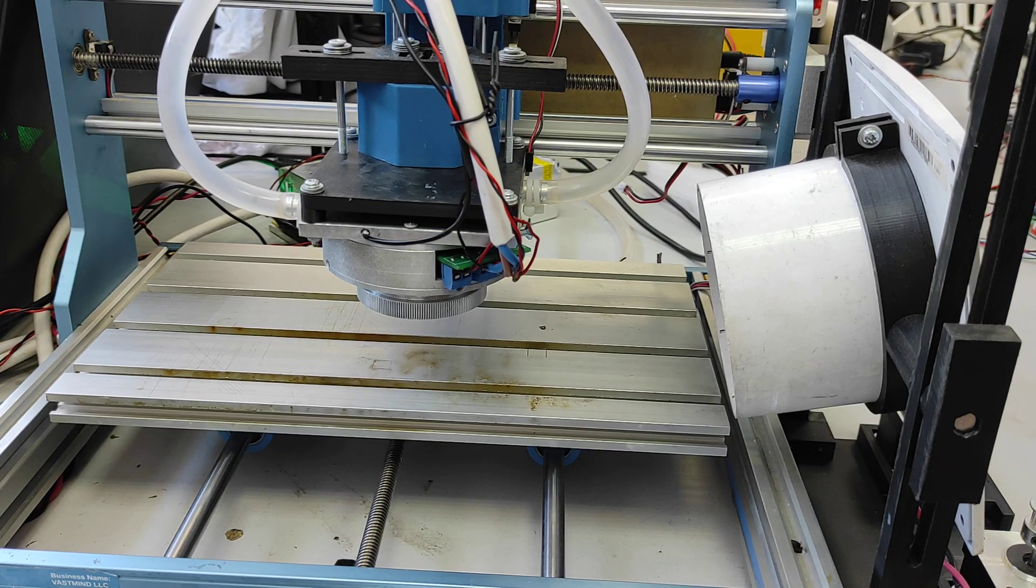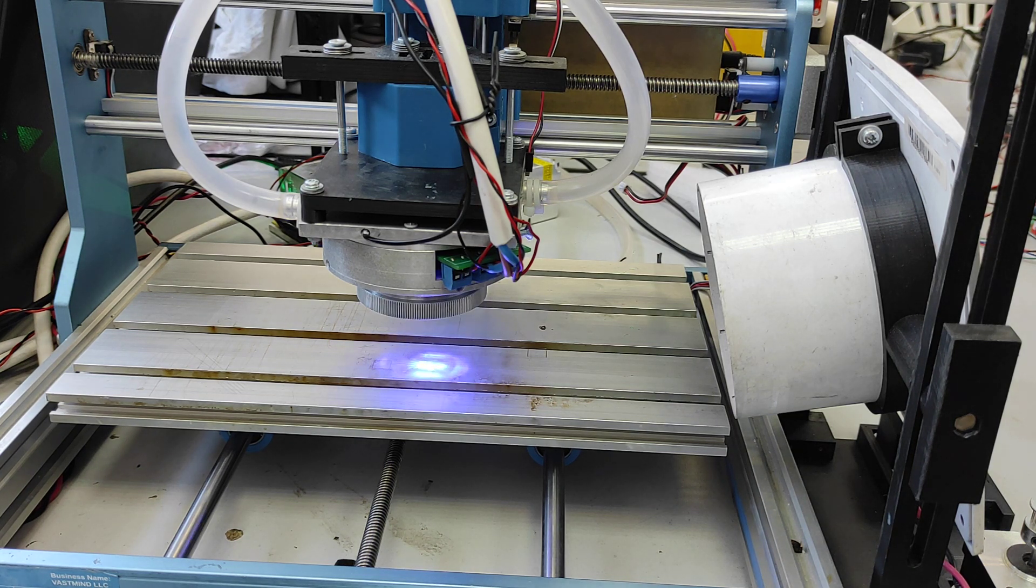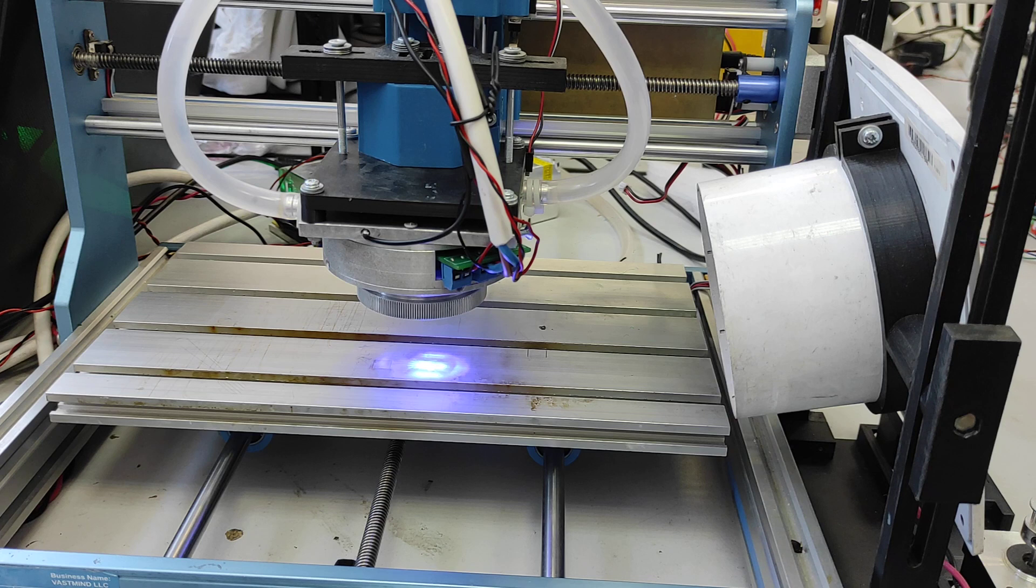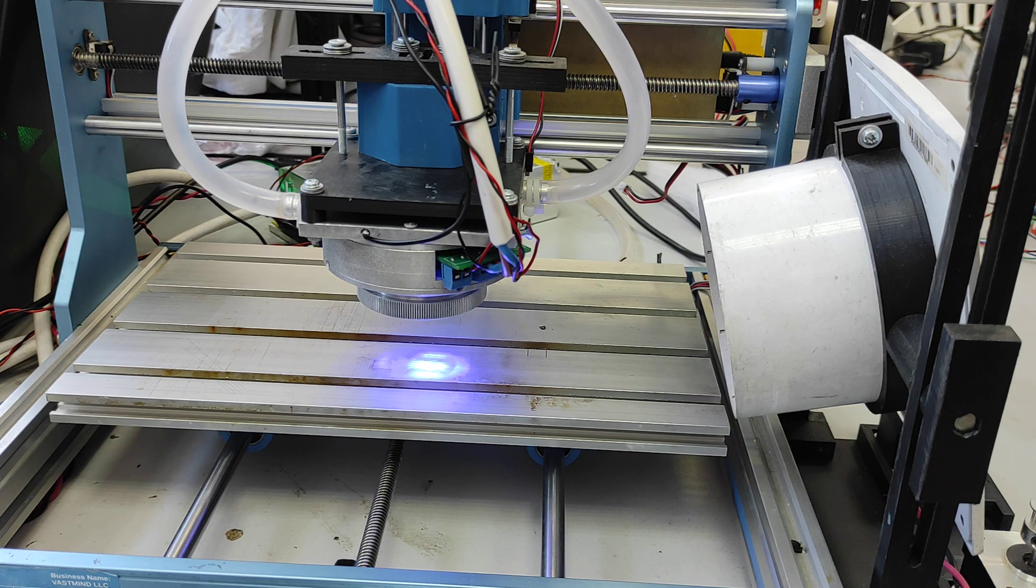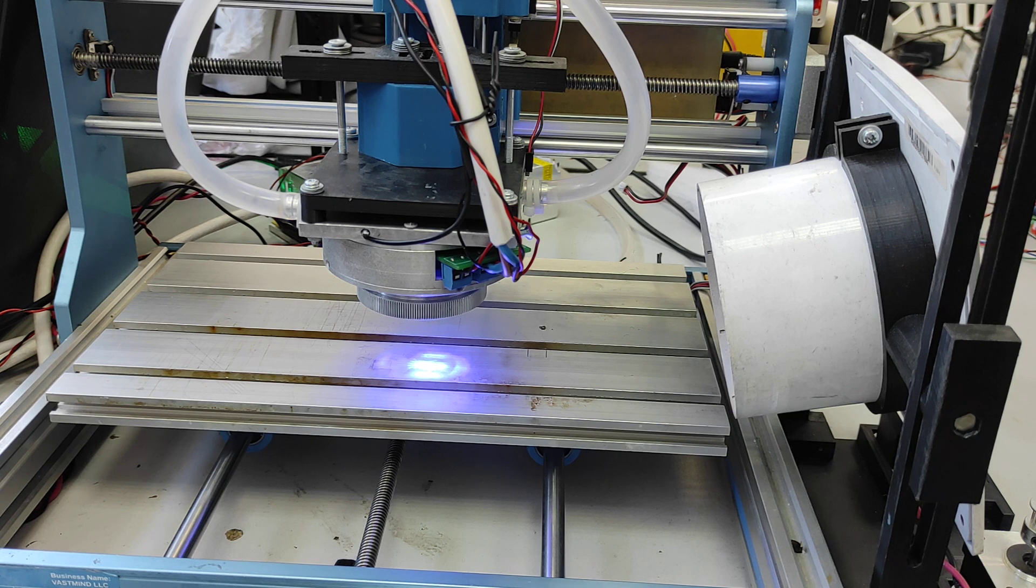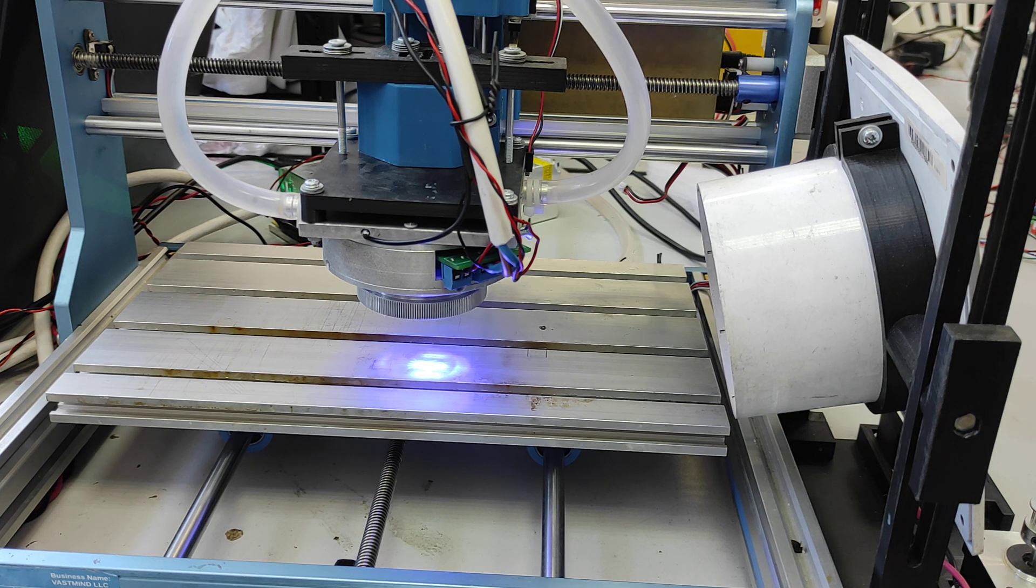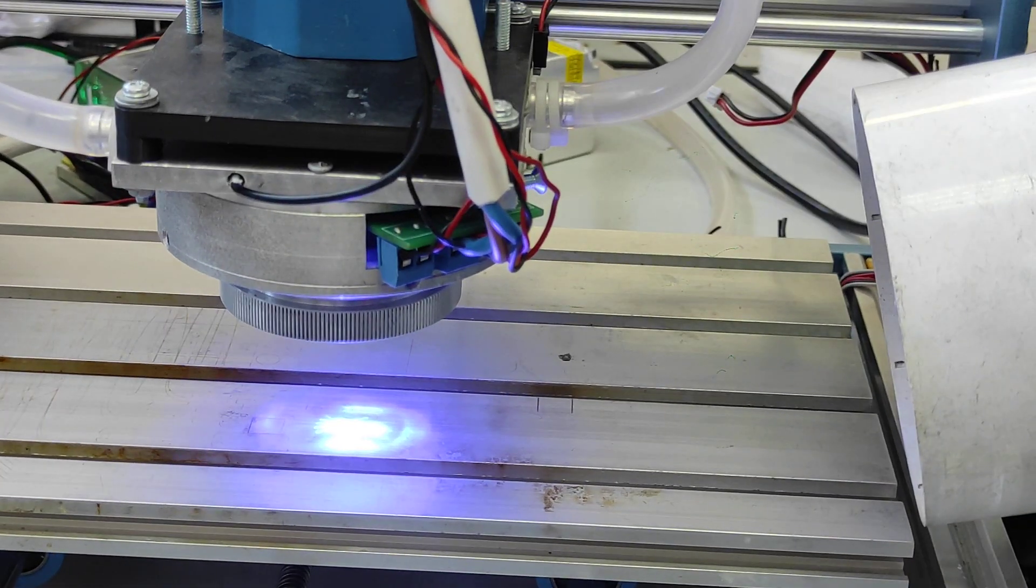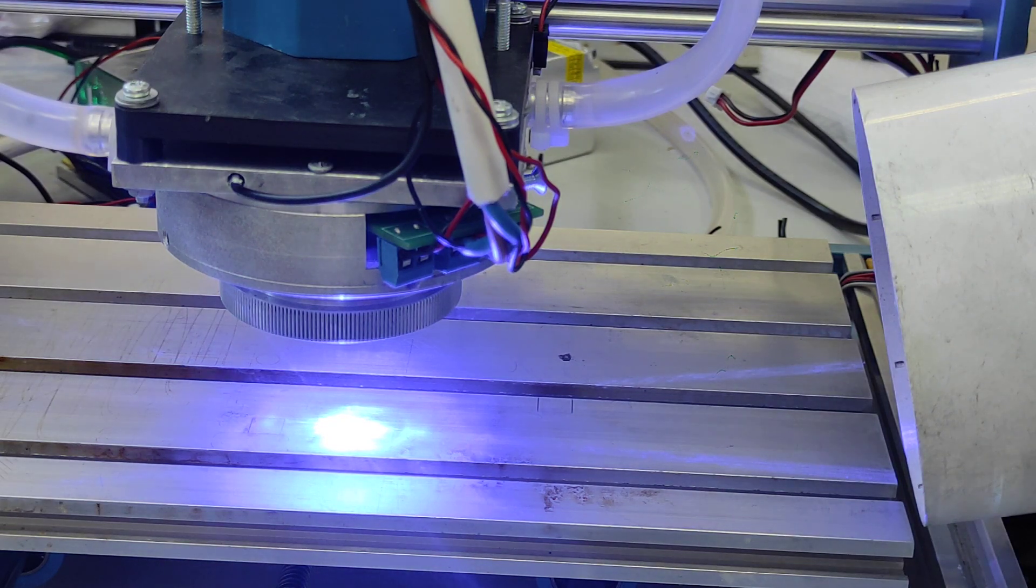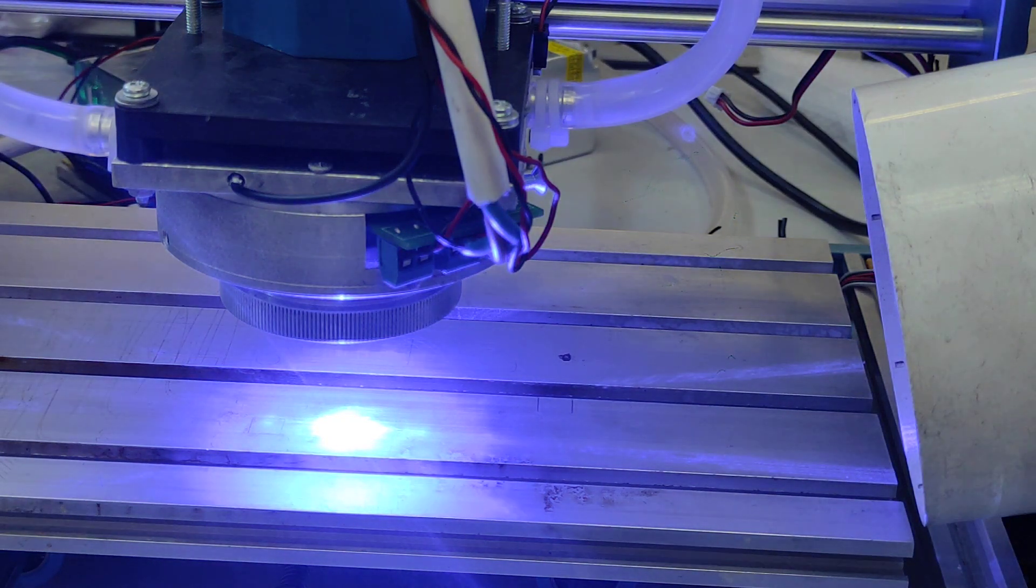Let's turn on the laser. It takes time to heat up. We are working on immediate on mode. Right now it takes time for current to grow to three amps. That's the working current, maximum current for this laser, and the voltage for this one is about 74 volts.